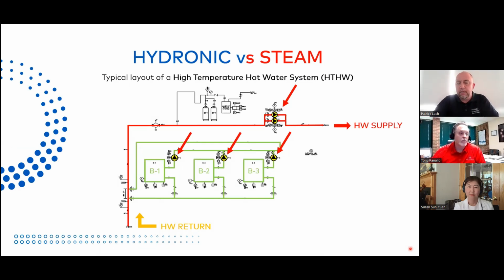So just the pumping, let's talk about the pumping. For a hot water loop, you need a pump for each boiler to get in the loop, and then you need a main pump that will feed the whole building, right? Compared to a steam system, where you need one feed water pump to feed from the DA or the main receiver tank directly to the boiler.